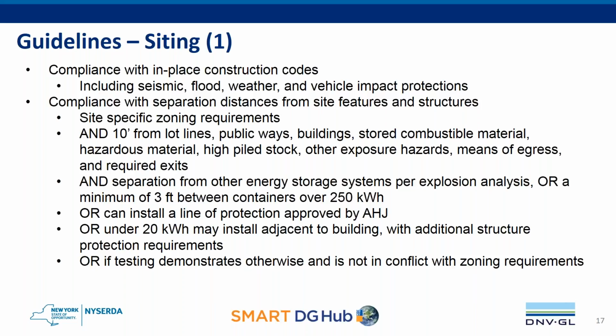So there will be site-specific zoning requirements. For instance, there may be a requirement to be X number of feet away from a path of egress or from a sidewalk. So this includes 10 feet from lot lines, public ways, buildings, stored combustible material, hazardous materials, etc. And in addition to that, there has to be separation from other energy storage systems on site in the case that the explosion analysis indicates that is required, or at least a minimum of 3 feet between containers over 250 kWh. Or you may install a line of protection, but it needs to be approved by the AHJ. And just as a note, since the explosion analysis is typically a requirement, if the line of protection is not supported by the explosion analysis, then it could be a non-starter.